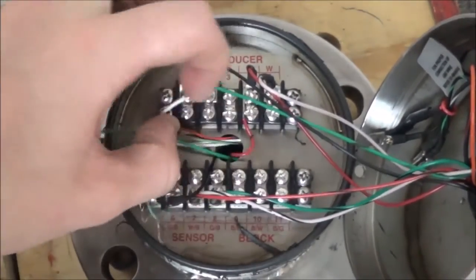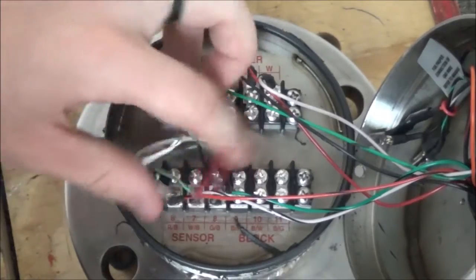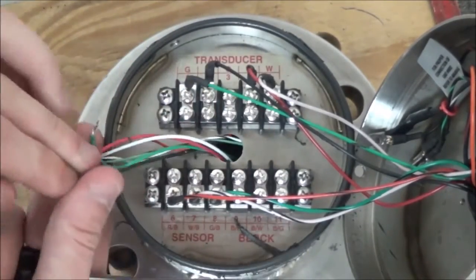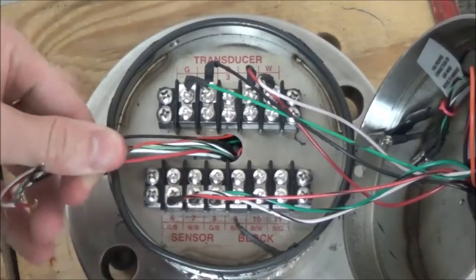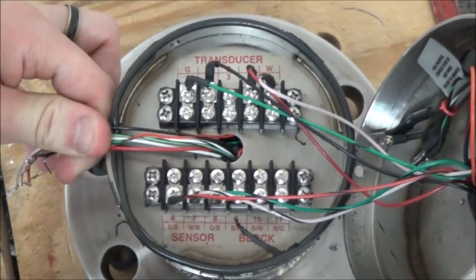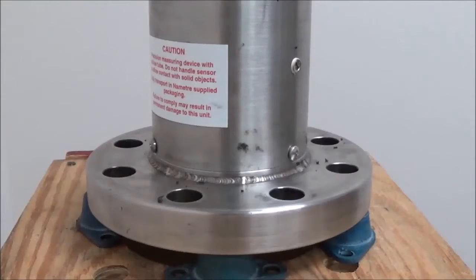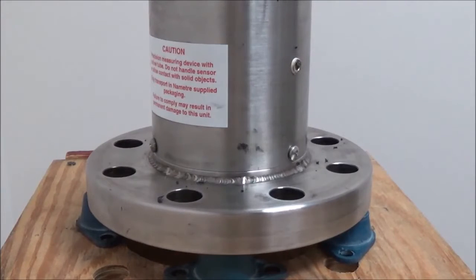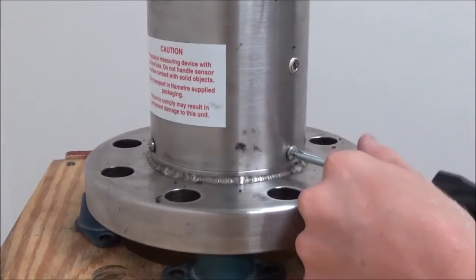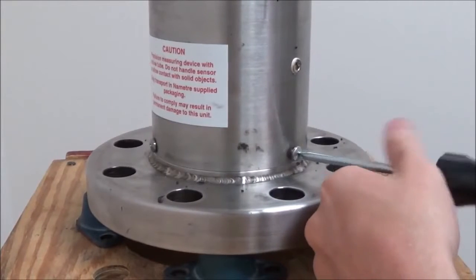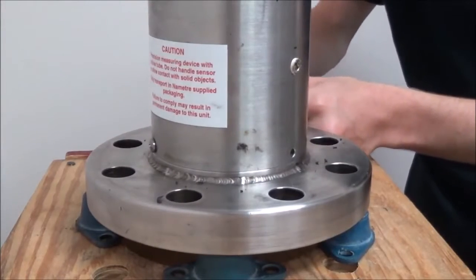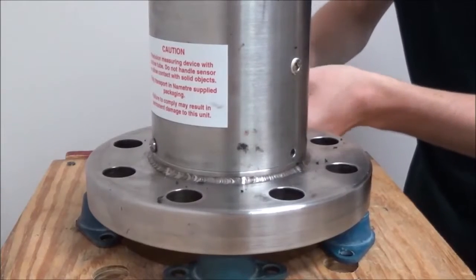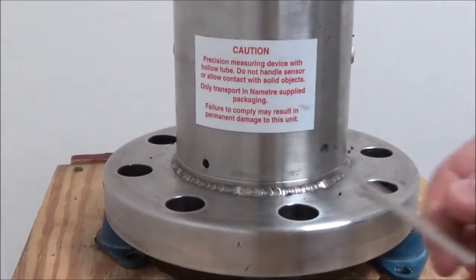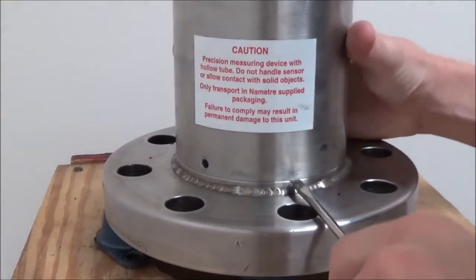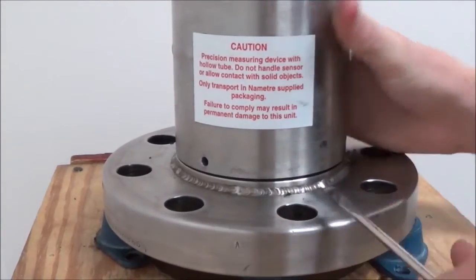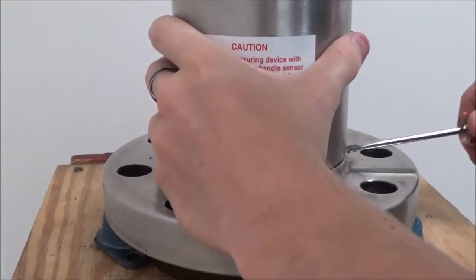Once all the inner terminal wires have been removed and unfurled, we now have access to the undermost sensor block. Put the wires over to the side, for we will be using them later. In order to get to the sensor block, remove the bottom 3 screws from the viscometer. Once the bottom 3 screws have been removed, it is recommended that a flathead screwdriver is used to pry off the sensor block cover.